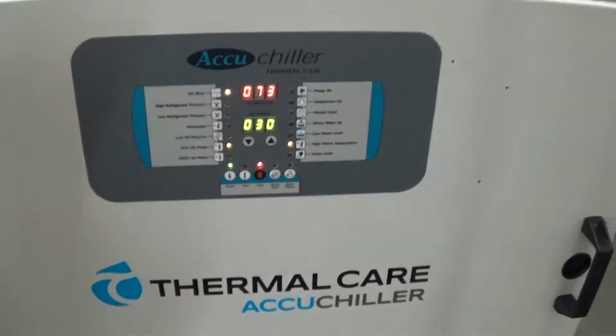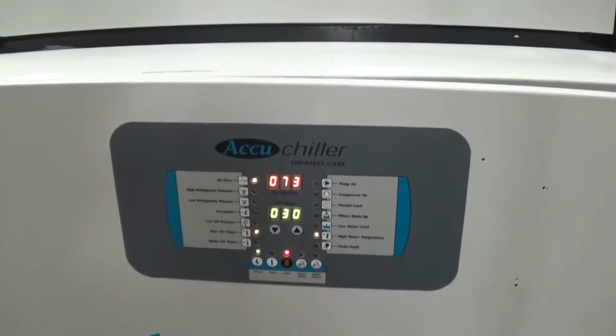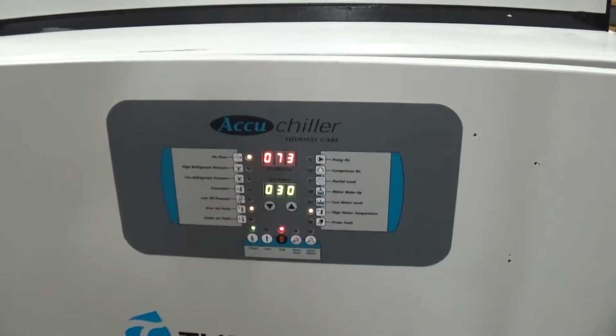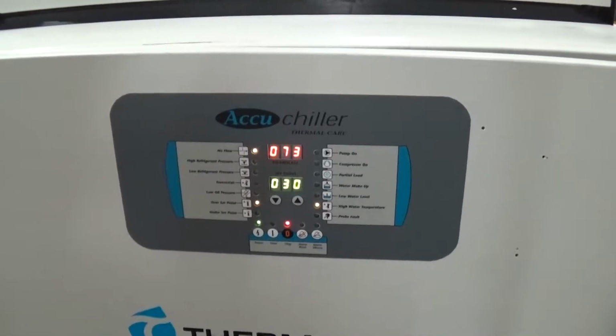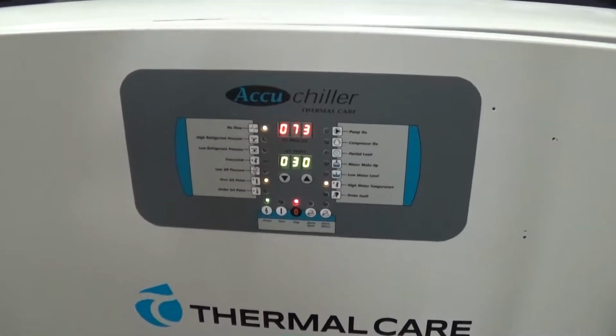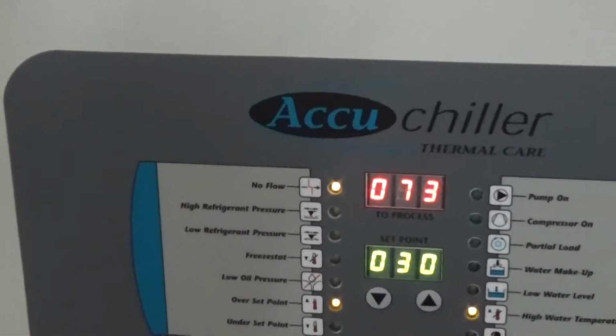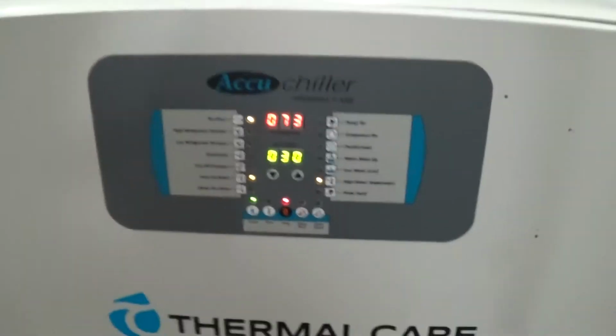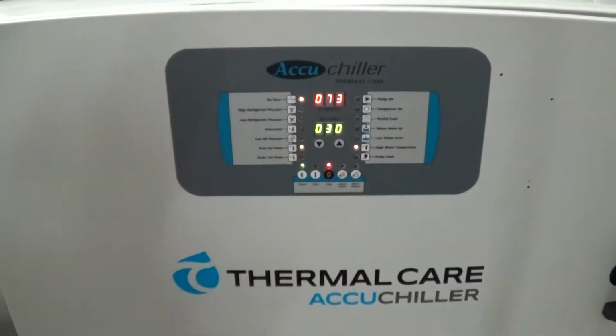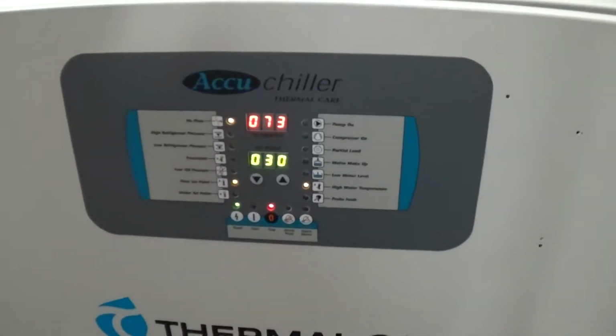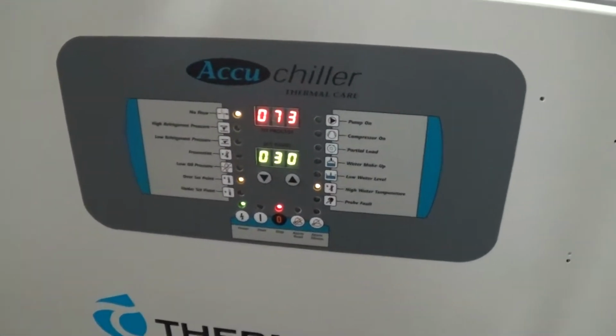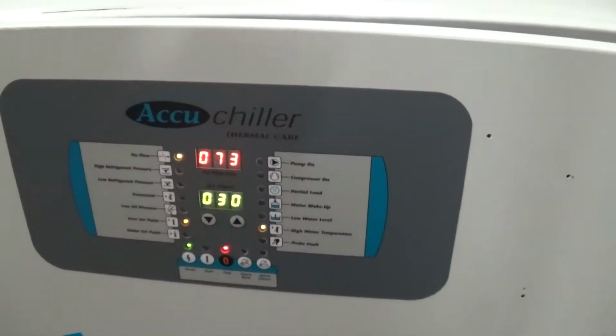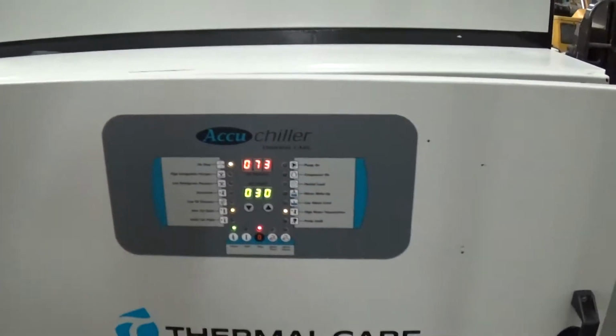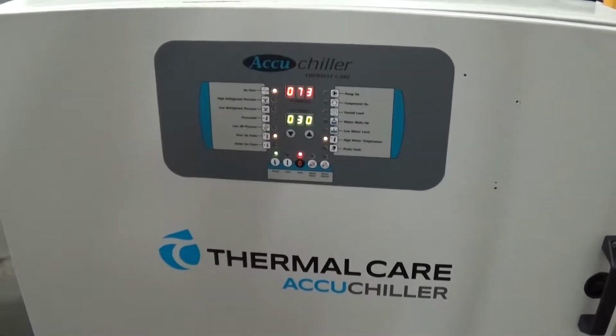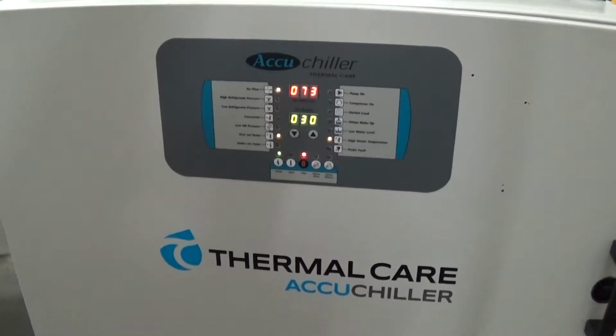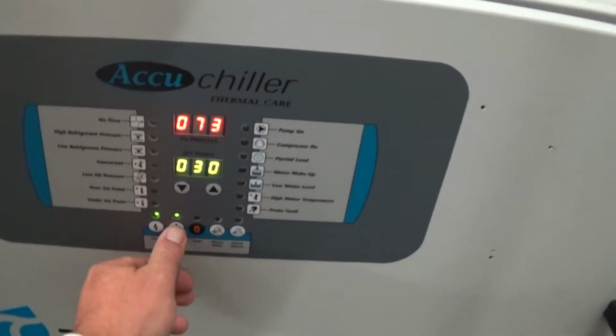Any temperatures below 48, you have to run a 40% glycol solution, or you risk freezing up and rupturing the heat exchanger in the chiller. Right now you can see it has no flow because we haven't turned the start button on yet, which will initiate the pump flow and turn the chiller on. In fact, when we press start now, because we're below set point, the compressor will come on and start cooling a second or two later. So let's just press start.